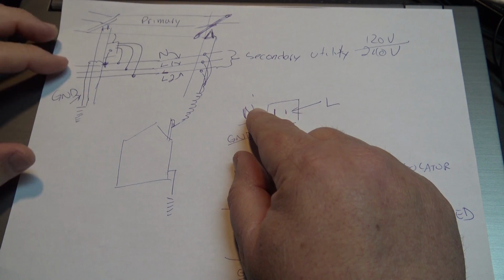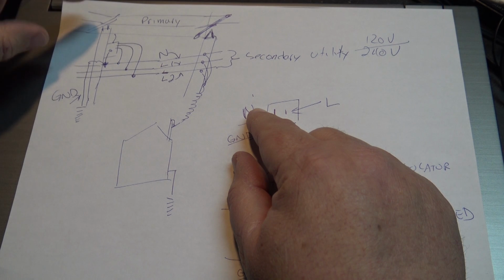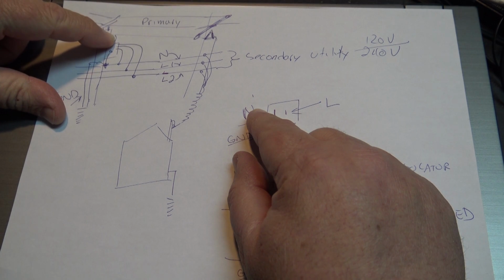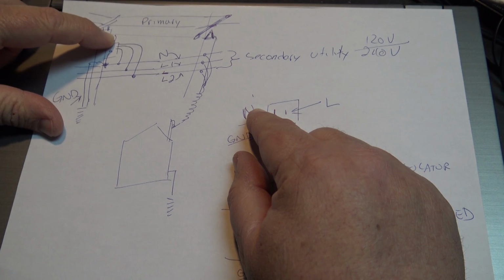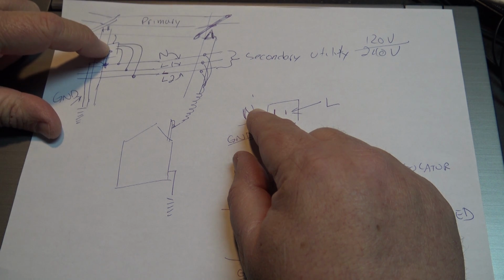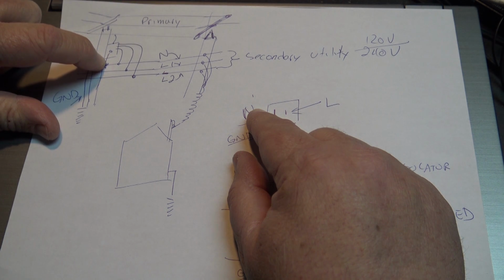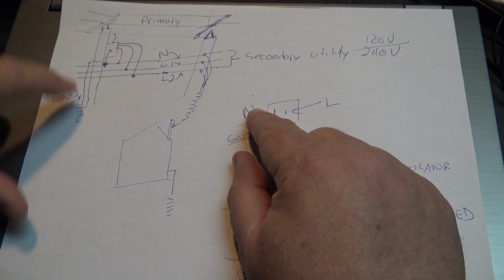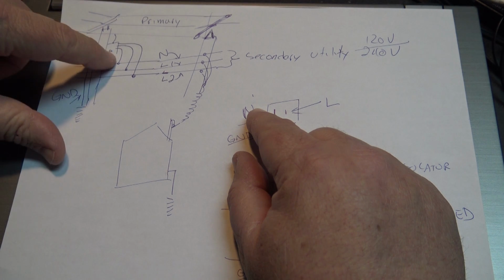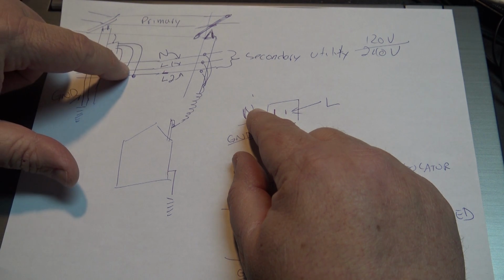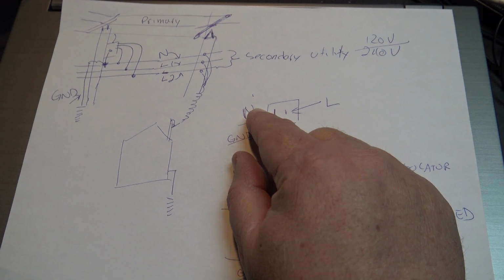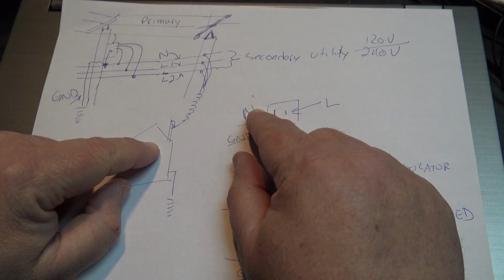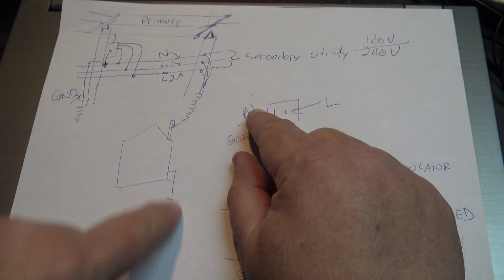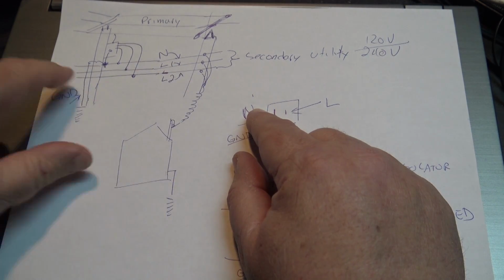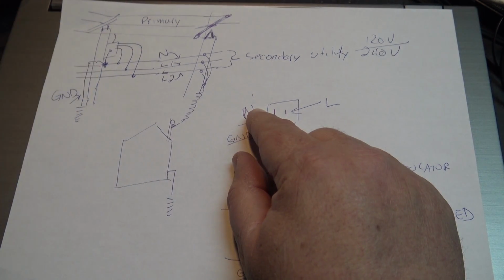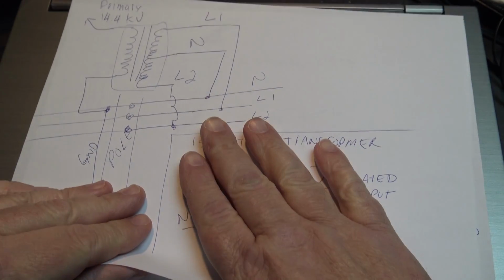Here's your utility transformer. And typically what they do is your primary will be connected to the primary winding of the transformer. The other side of that primary winding is connected to the neutral, which is also connected to earth. And then you've got your secondary windings, your neutral, and your two, line one and line two. That's connected to your house. Now your house also has its own independent ground on it. But remember that the neutral is tied to ground at the utility pole, as we can see on this schematic.